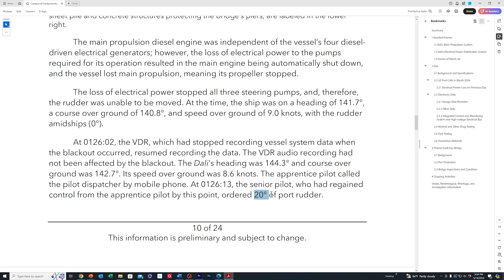The emergency generator started and connected to the emergency bus, so its breaker would have closed — that could happen shortly after lost electric power. Now, they're not saying how long it was, but it must have been at least a minute or so, maybe a minute and a half, because we saw how long it took for the lights to come back on. These emergency generators are supposed to kick in in like 45 seconds.